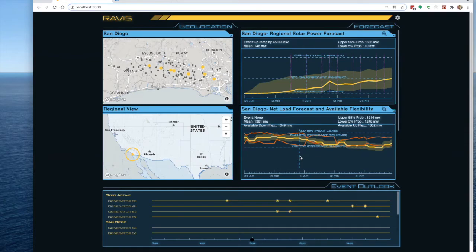Similarly, on the downward side, as the day progresses, we have solar power increasing, ramping up, and then the net load is ramping down. So that's why we see the downward flexibility reducing and reducing. And at some point, it so happens that many of the conventional generators are at their minimum generation, min gen, so they're not able to move further down. So the available downward flexibility is actually lacking. In those situations, one might expect renewables to be curtailed. So these are some insights that one might get from a comprehensive situational awareness, including other data.